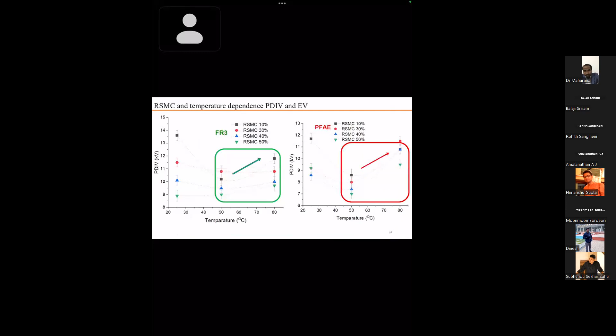Sir, the next one is about ester fluid. We say it can hold higher moisture content, which can increase the lifetime of paper. Should the moisture holding capacity of an insulating fluid be higher or lower? It is a controversial statement. If there is moisture in the oil, it will go to the paper, and if there is moisture in the paper, that is already dangerous. So we definitely try to reduce water content as much as possible in the devices, and during installation we need to protect against it.